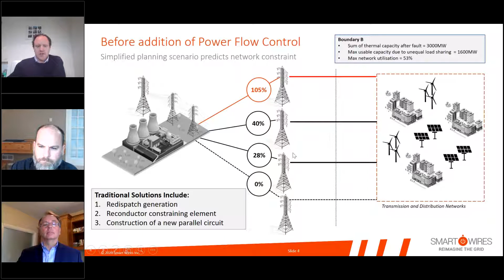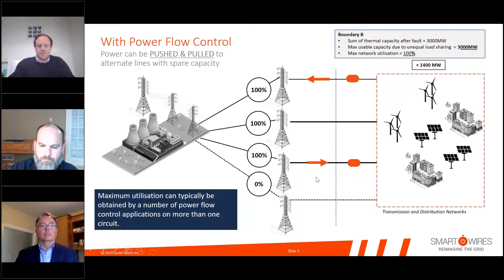Traditional solutions to this might be redispatching generation, reconductoring the constrained element on the top, or even building a new circuit between the generation and load center. And what power flow control really does is help you to maximize the utilization, or even out the power flows across those intact paths. In one way, you can push power off constrained elements onto underutilized lines, or in another way, you can install a flow controller on a lightly loaded line and pull power down that. And in that way, you can move towards this theoretical 100% maximum utilization post contingency, with optimized deployments across the network.